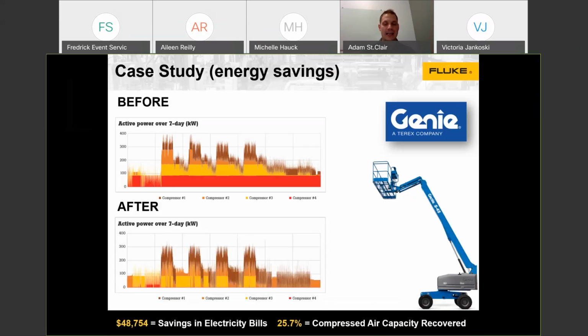We asked: if we can help you identify and fix all the compressed air leaks in your manufacturing process at one facility, what kind of savings will that have? So we took some Fluke power quality meters and hooked them up to each of the 4 compressors in their production process. We measured the kilowatt-hour energy usage on those compressors over a 7-day period, giving us a baseline for what those systems were costing in energy usage over a week.